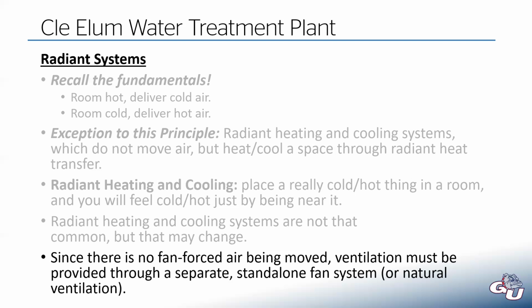An important note with radiant systems: so far we've talked about how fresh ventilation air is typically delivered through the air handling unit itself, and you have to run those fans all the time to keep delivering that ventilation air. Because radiant systems aren't moving any air, you have to provide ventilation through a separate standalone system, called a dedicated outside air system.